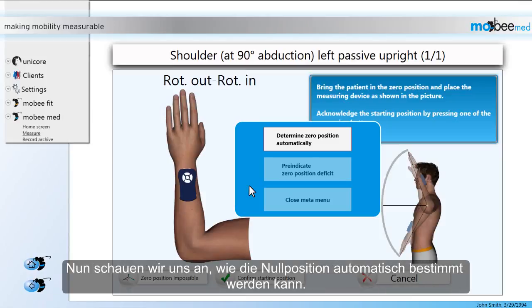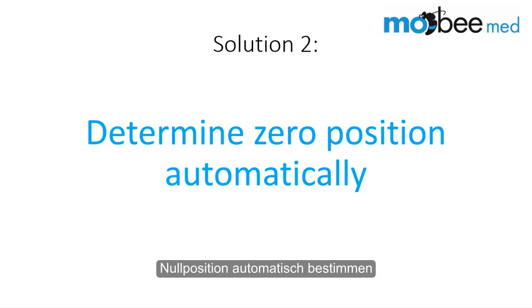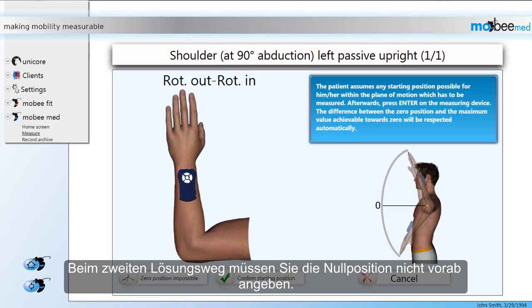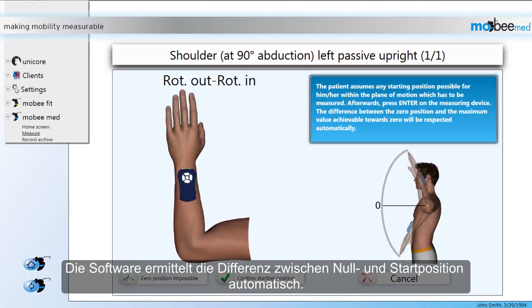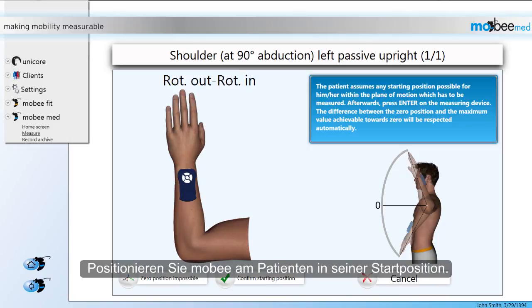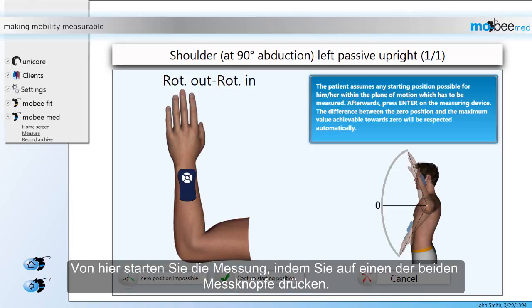Now we are going to take a look at how to determine the zero position automatically. When you have selected the second solution, you do not have to pre-indicate the zero position. The software automatically determines the difference between zero and starting position. You simply place mobee on the patient in his starting position. From there you start the measurement by pressing one of the measuring buttons.